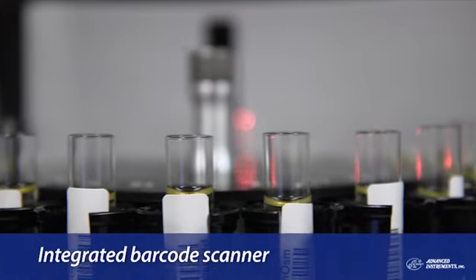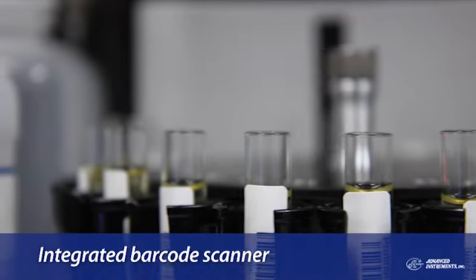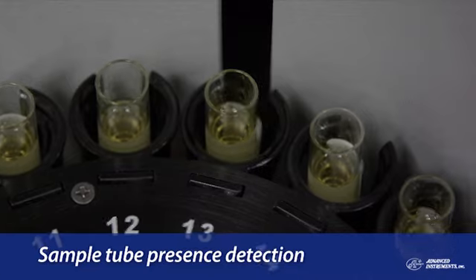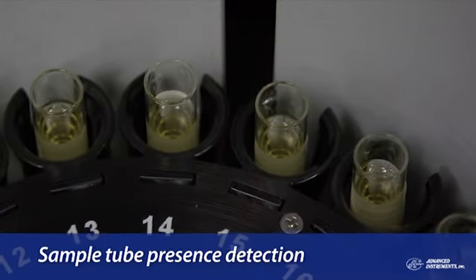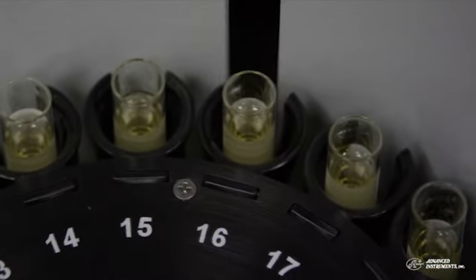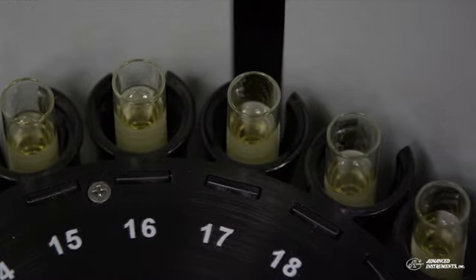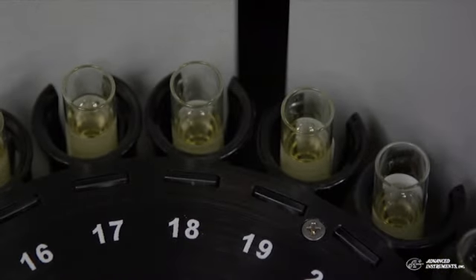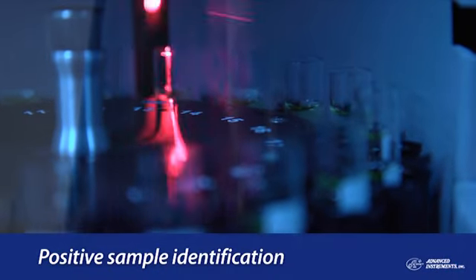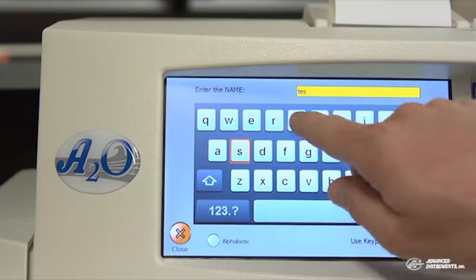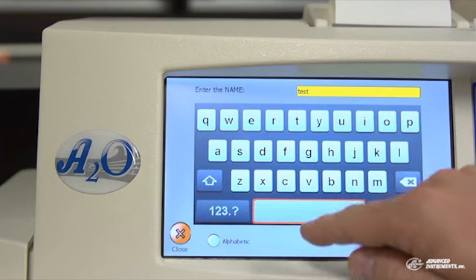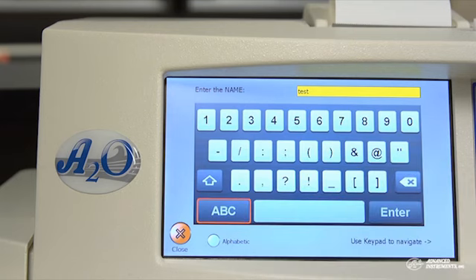The A2O comes equipped with an integrated barcode scanner and tube presence sensor. The A2O performs an initial scan of the primary sample carousel, identifying both the number of sample tubes present and the barcode ID. The sample identification is confirmed again immediately before the sample is processed, providing positive sample identification. The scanner can be turned off if no barcodes are used, and sample IDs can be entered manually through the keypad function of the software interface.